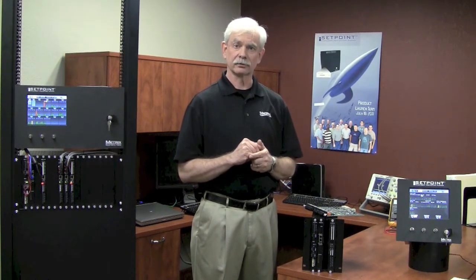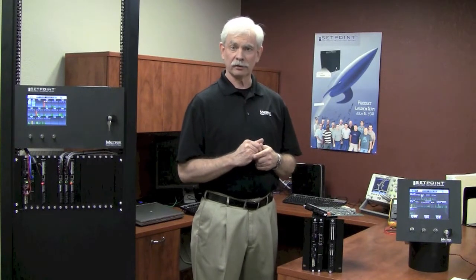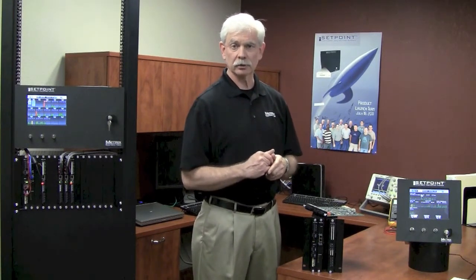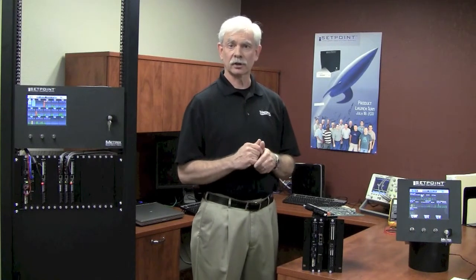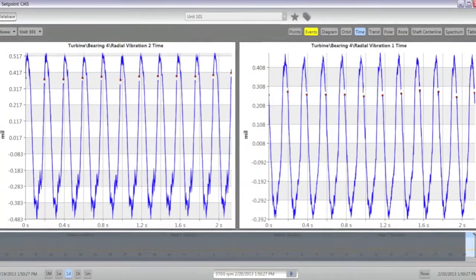As you probably know, PI ProcessBook was designed to look at process data, so it's very good at displaying trends, statuses, and other types of real-time data. It really was not designed initially to store or display high-speed waveforms. With Setpoint CMS software, what we've been able to do is use the PI Historian as a repository for this high-speed waveform data and use our Setpoint CMS software as a visualization tool to actually see that data.